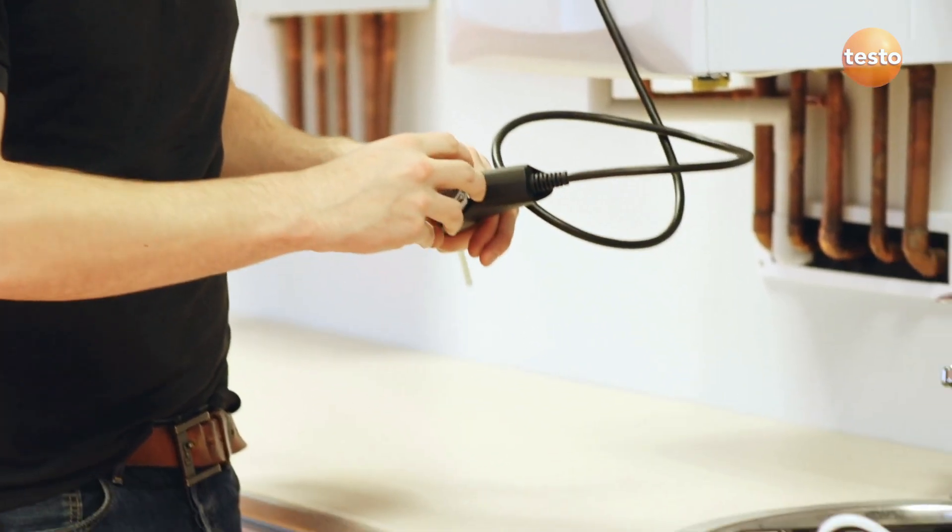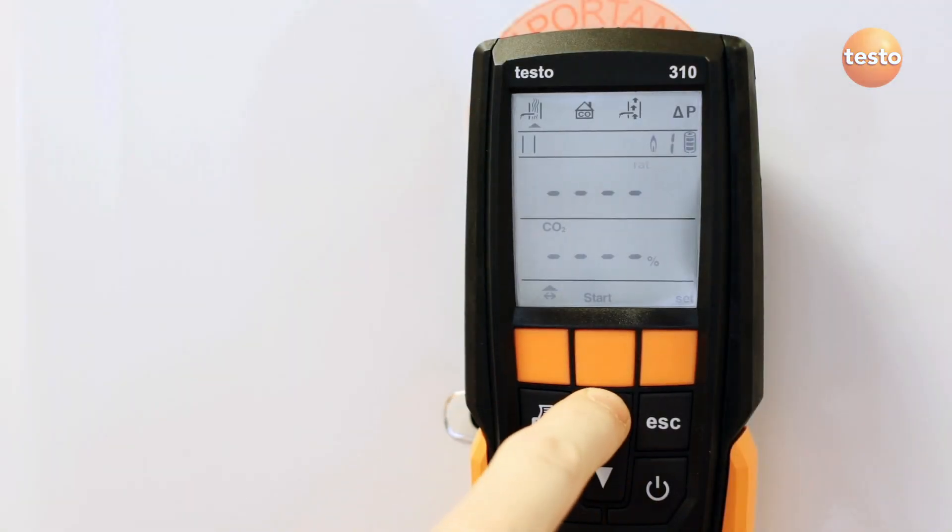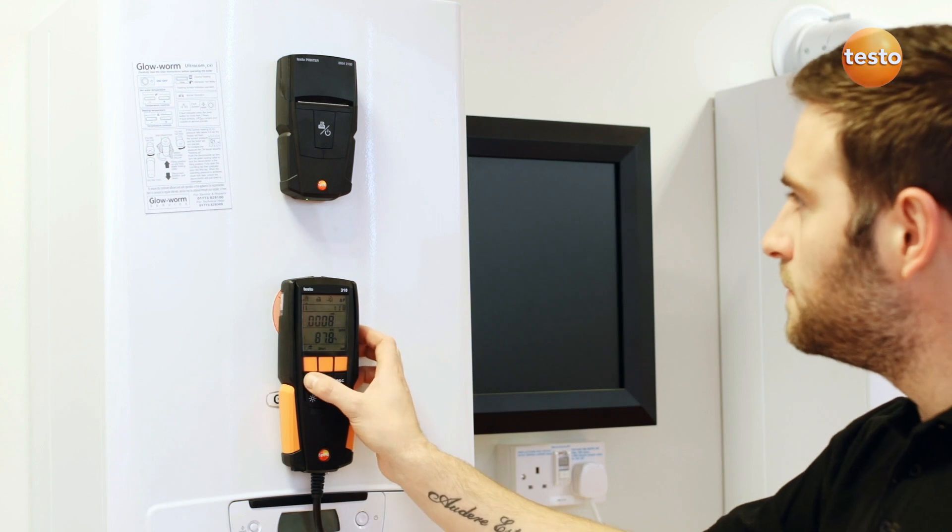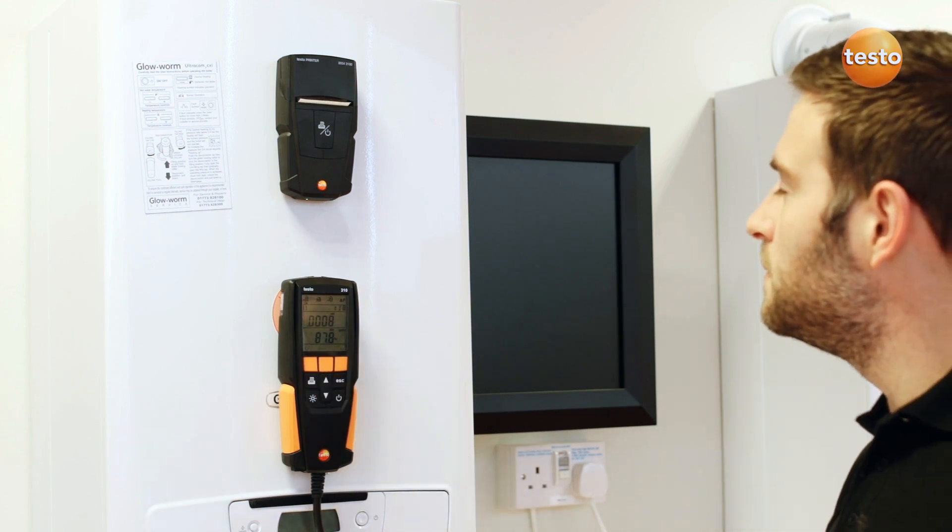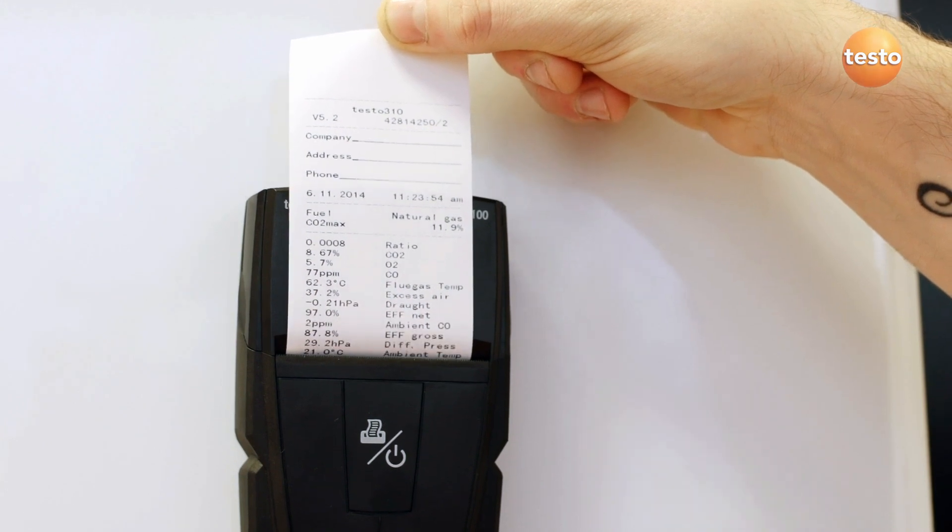The pressure and draft readings are held in the analyzer as long as it's switched on. The pressure reading is labeled P2 and draft would be stored as P1. Now when the ticket's printed, it will include pressure measurements as well as the associated flue gas readings.